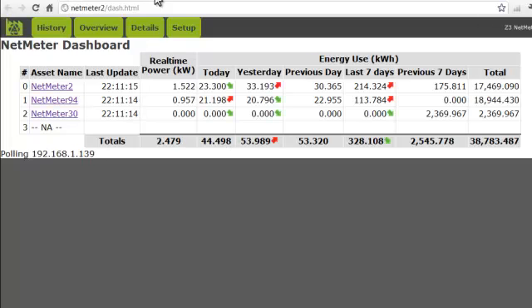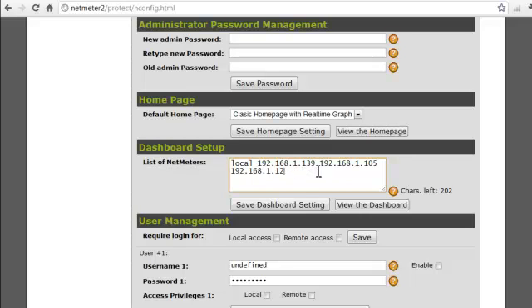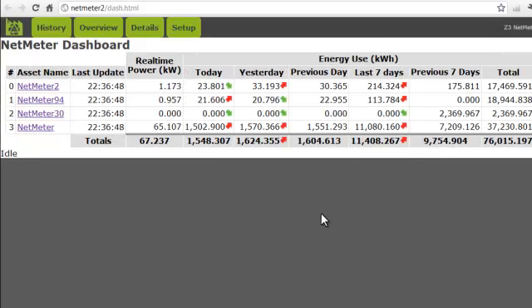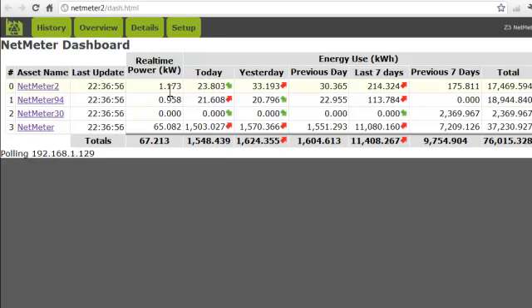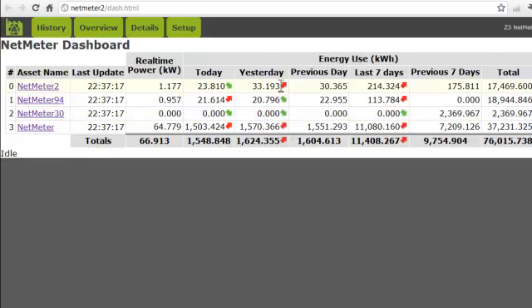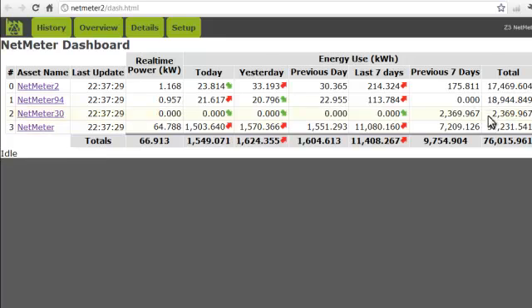Now I'll go back and fix the mistake and then view the results. The dashboard shows a spreadsheet-style information display that is being continuously updated. It shows real-time power demand, how much energy has been consumed so far today, and an indicator about how this is trending. The Yesterday column shows the energy consumed yesterday and a trending arrow relative to the previous day. The 7-day columns are similar but for a 7-day period. Lastly, you can see the total energy consumed since the NetMeters were placed into service. The last row of the spreadsheet sums up all of the data and shows the overall trending.